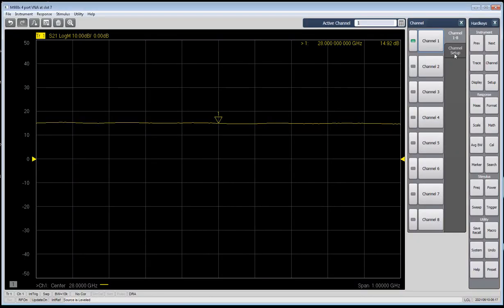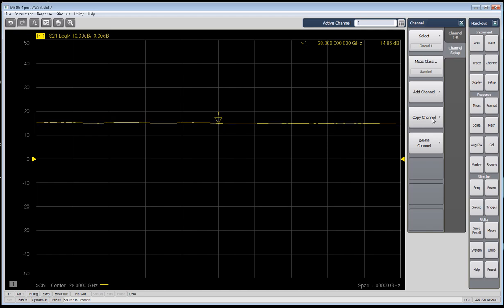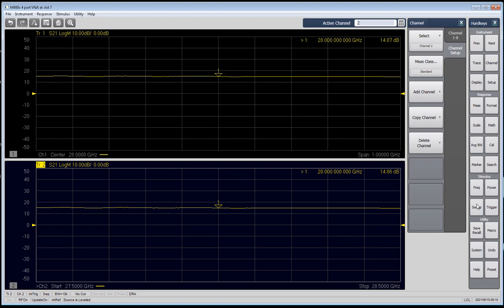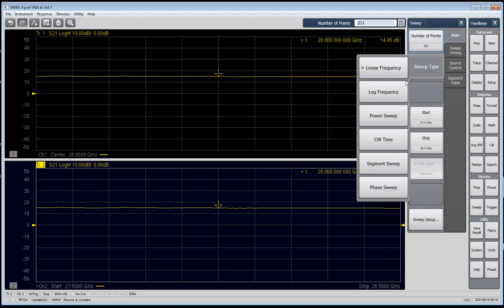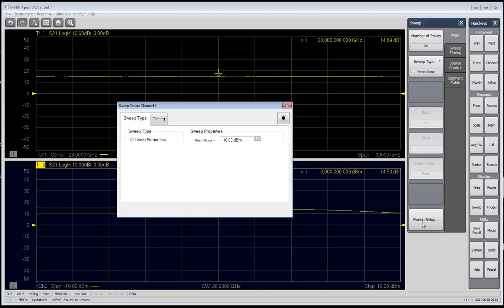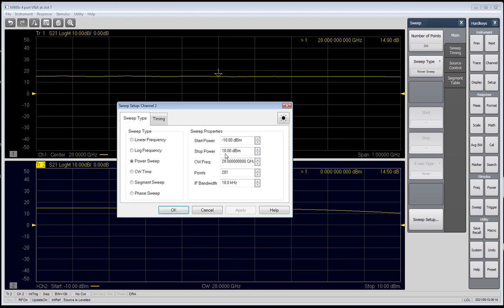Now this is normally the part where you would connect your eCal and perform a basic S-parameter calibration, but since I'm thousands of miles away from the instrument, you'll just have to trust me that this instrument is calibrated, and I've recalled a calibrated state file, so I'm going to skip that step. Now that channel 1's all set up, let's go to the channel setup option and copy all of the settings into a new window. In this new window, we want to do a power sweep on our amplifier, so we'll go to Sweep and then select Power Sweep under the Sweep type. And then going into the Sweep setup menu, we're going from minus 10 to 10 dBm, centered around the 28 GHz of this amplifier.